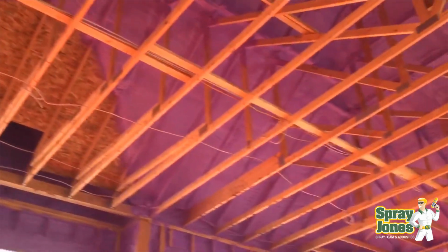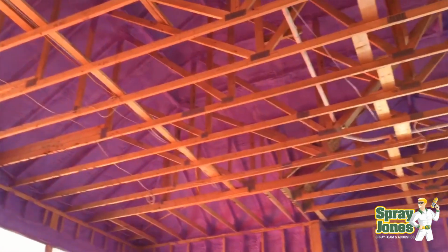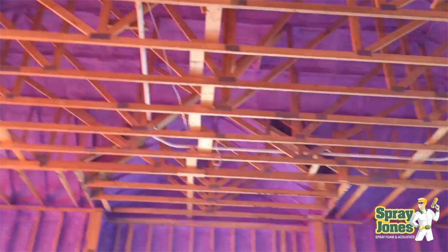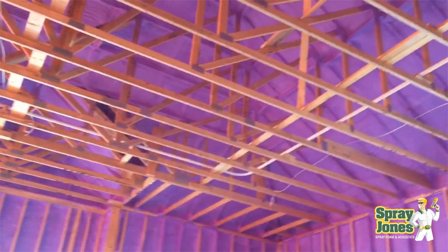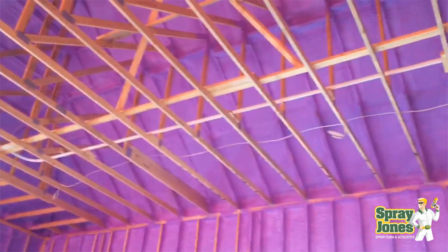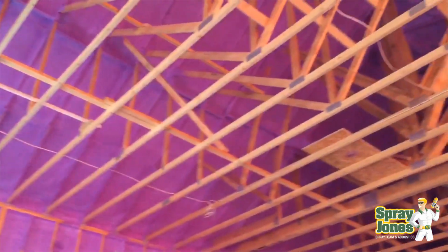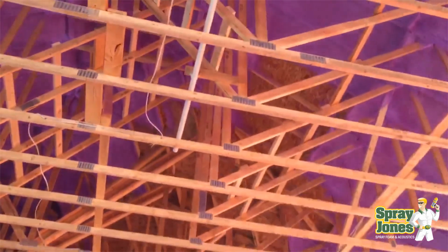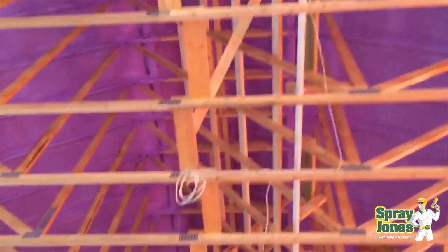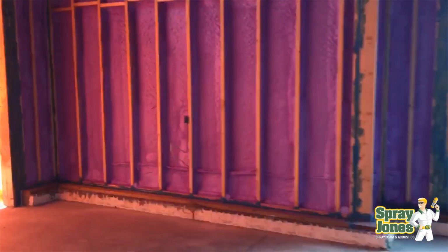So I've shown you from the details before of those pictures of the temperature in the attic and the humidity levels. The attics are not at a substantially higher or in the wintertime lower temperature than the thermostat. I've always told my clients 1 to 2 degrees thermostat temperature. And they usually are maintaining the same humidity levels. If you've sprayed the roof deck and you've sprayed the walls and you have a foam box for your structure, whether it's commercial or residential or what have you, the space is going to equalize based on what the HVAC makes it. Where you place the drywall after that really doesn't have a huge bearing on separating out temperature level and humidity level.